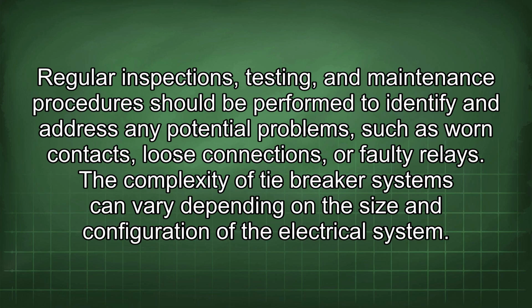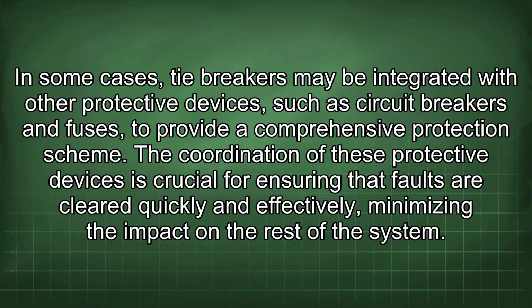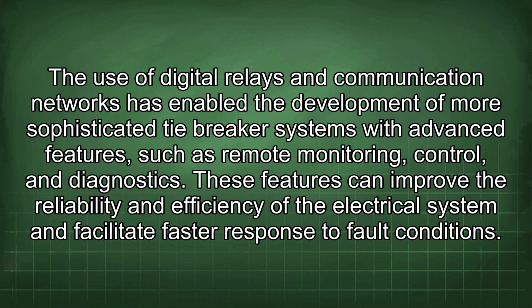The complexity of tiebreaker systems can vary depending on the size and configuration of the electrical system. In some cases, tiebreakers may be integrated with other protective devices, such as circuit breakers and fuses, to provide a comprehensive protection scheme. The coordination of these protective devices is crucial for ensuring that faults are cleared quickly and effectively, minimizing the impact on the rest of the system. The use of digital relays and communication networks has enabled the development of more sophisticated tiebreaker systems with advanced features, such as remote monitoring, control, and diagnostics. These features can improve the reliability and efficiency of the electrical system and facilitate faster response to fault conditions.